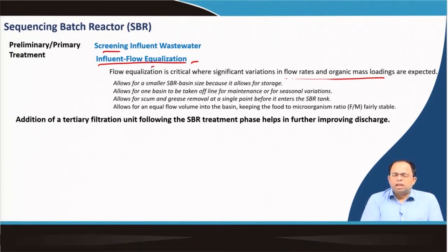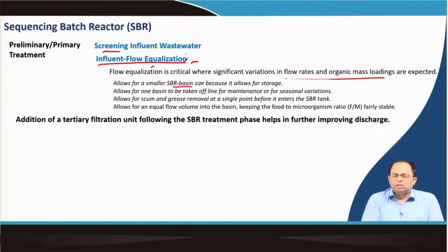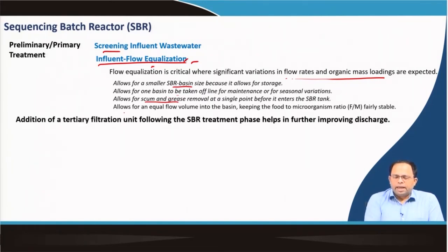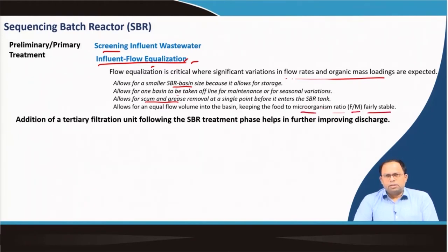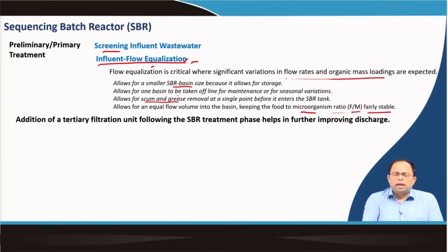The presence of the equalization tank also reduces the size of the SBR basin. It allows maintenance work on the basins while incoming wastewater is stored in the equalization tank. It also allows scum and grease removal at a single point before entering the SBR tank, and it ensures an equal volume flow into the basin, keeping the food-to-microorganism ratio (FM ratio) fairly stable.